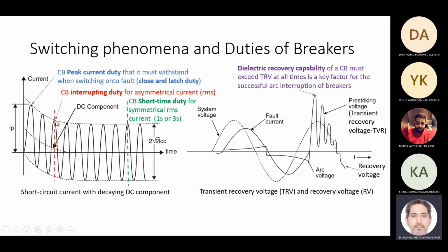The second specification by the manufacturer of a circuit breaker is called the interrupting duty, or the current that the circuit breaker can break at the contact opening time. A fault happens, then a relay takes time and gives, let's say, a breaker command. A breaker is a mechanical device and will take time until it opens. So this is the time at which the breaker contacts start to open, and we should use this one for rating. This is the current that includes both AC and DC components, the DC component on top of the AC component. So it should be able to break this current, and this is where they specify the breaking capacity of the breakers.